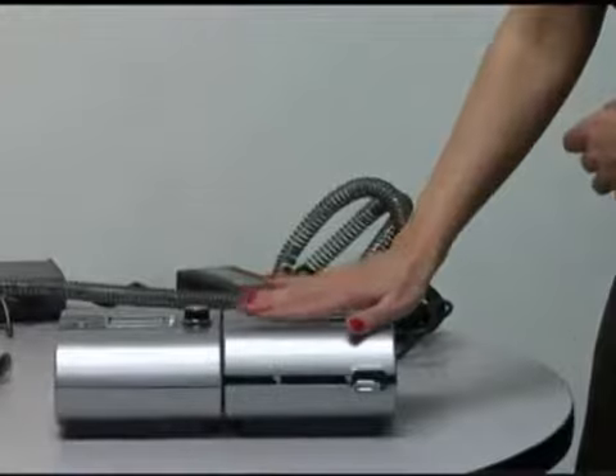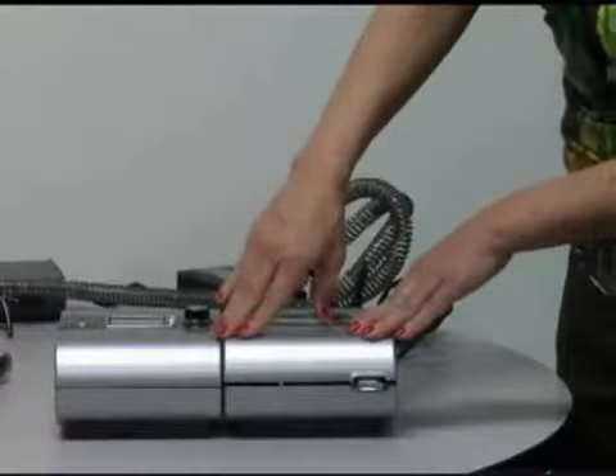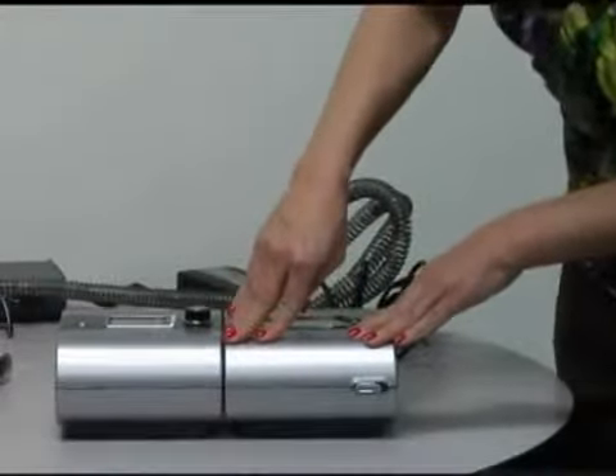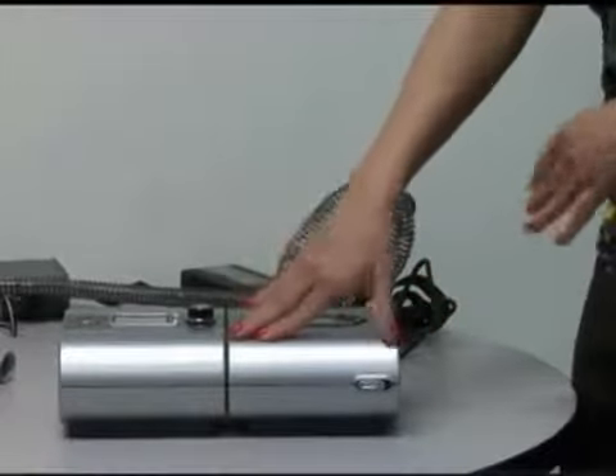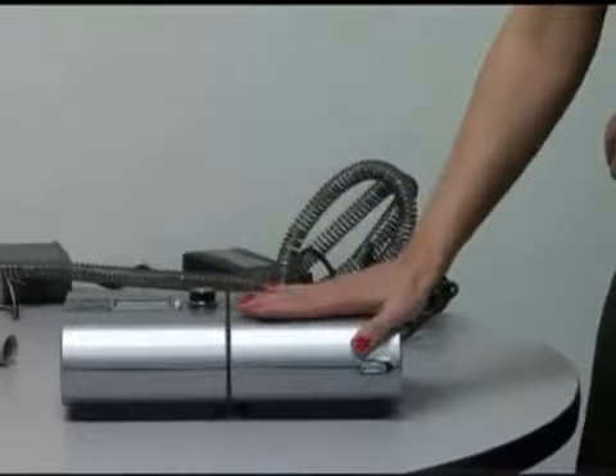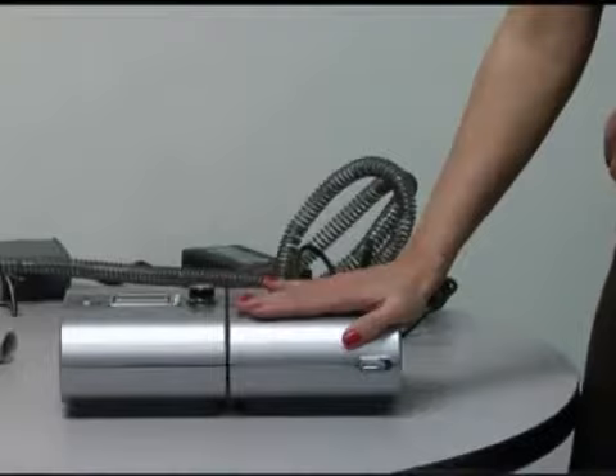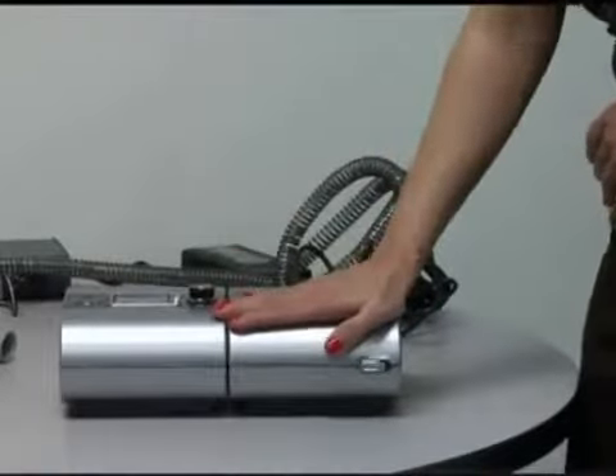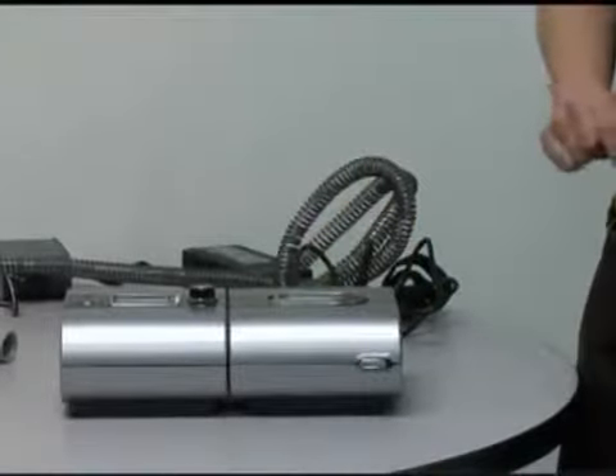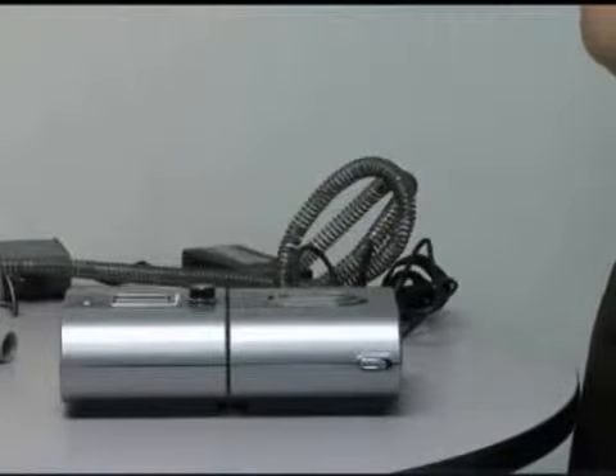The hardest part of this machine is to make sure you have this lid closed all the way. That latch should snap back. If that latch does not snap, this machine will leak air and it will turn off. So close that lid all of the way. The latch snaps back and your machine's all set and ready to go.